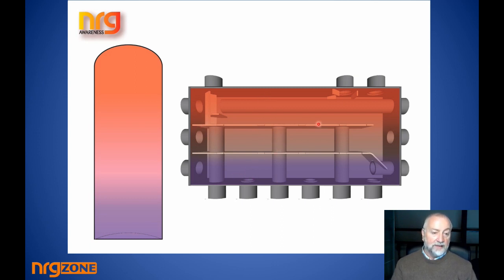But you also have waveguide plates or separation baffle plates that prevent the hot water from getting towards the colder water until it's past each of the zone opportunities. The zone opportunities could exist in any chamber or any connection off the top port. And likewise with the return, the cold water can't be shunted back up to meet with the top water because of three principles: because of stratification, because the plates are preventing it, and also because the water has been taken away from the bottom zone area by the boiler or boilers that are connected. So you have all the benefits, like you've got your cake and you're eating it, you have all the benefits of a buffer tank, and yet you've got a fraction of the cost and a fraction of the size, and you also have the additional ability to have multiple ports that can be used for many different reasons.